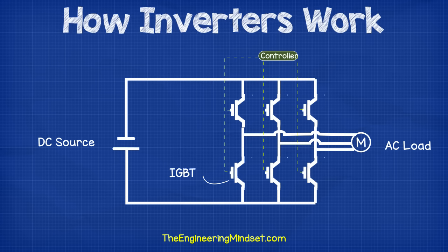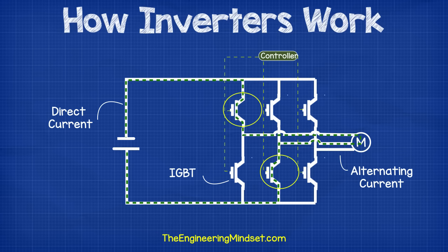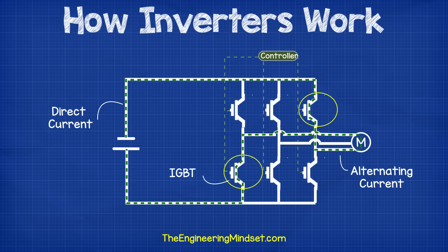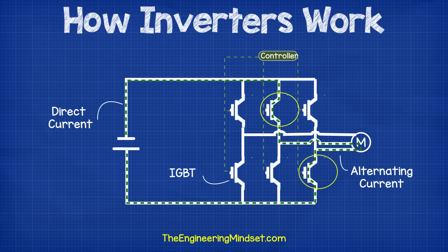Let's look at a three-phase example for a motor. This circuit has a DC source and an AC load, and to convert the direct current into alternating current, there are a series of IGBTs connected to a controller. The controller sends a signal to each IGBT telling it when to open and close, and these IGBTs are paired together. When the circuit is powered up, the controller switches pairs of IGBTs to allow current to pass through them for a set amount of time, so that the motor experiences an alternating current — in this case in three phases.